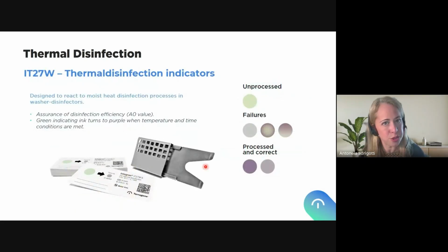Okay, so what is the solution we give for this specific step? Because it has no relationship at all with washing. Here we expect to kill or inactivate microorganisms, not to remove them. Removing them is washing. So here we want to corroborate the combination of time and temperature to guarantee the A0 value or level of disinfection. So this is the IT27W line of thermal disinfection indicators. They are designed to react to moist heat disinfection processes inside washer disinfectors. They assure the efficiency or the level of A0 value or of disinfection.